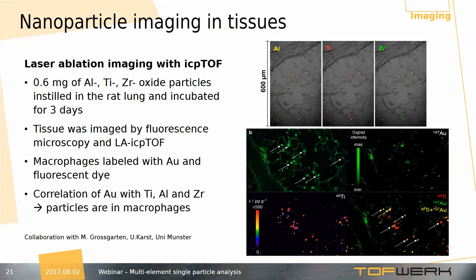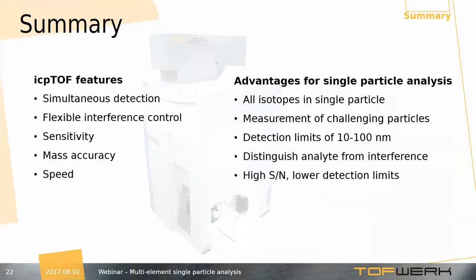This was the last application I wanted to show you. To summarize, the important features of our instrument for single particle analysis include: simultaneous detection, which gives information about all isotopes even in single particles, opening a completely different world for single particle ICP-MS applications; flexible interference control, giving flexibility in dealing with different interferences and measuring challenging particles; sensitivity sufficient to measure particles in the size range from 10 to 100 nanometers; mass accuracy to qualitatively distinguish analyte peaks from interfering peaks; and speed, which increases signal-to-noise ratio and improves the detection limit.